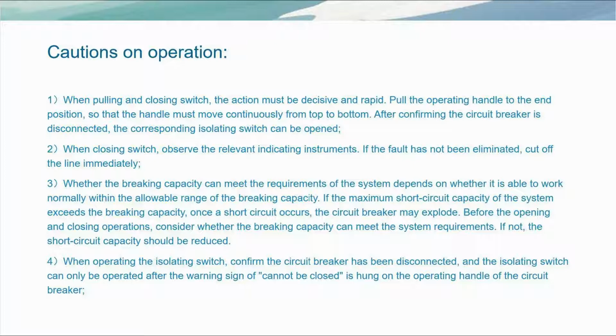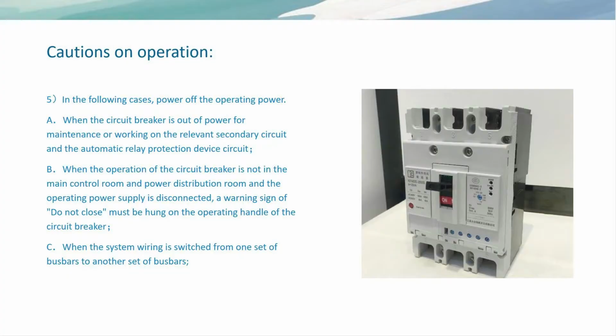4. When operating the isolating switch, confirm the circuit breaker has been disconnected, and the isolating switch can only be operated after the warning sign of "cannot be closed" is hung on the operating handle of the circuit breaker. 5. In the following cases, power off the operating power. A. When the circuit breaker is out of power for maintenance, or working on the relevant secondary circuit, and the automatic relay protection device circuit.